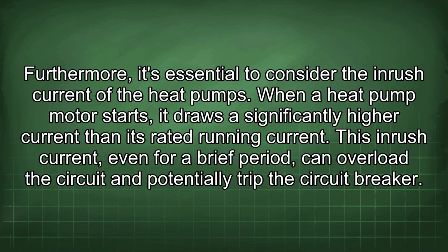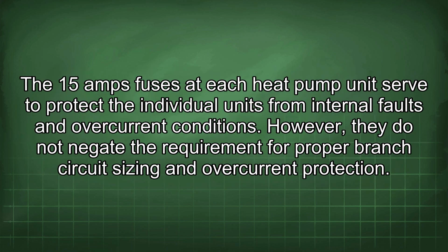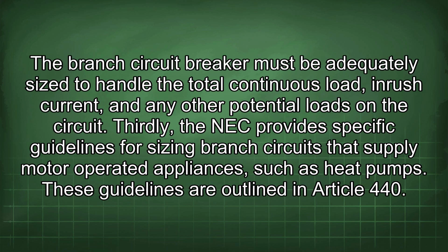Furthermore, it's essential to consider the inrush current of the heat pumps. When a heat pump motor starts, it draws a significantly higher current than its rated running current. This inrush current, even for a brief period, can overload the circuit and potentially trip the circuit breaker. The 15 amps fuses at each heat pump unit serve to protect the individual units from internal faults and overcurrent conditions. However, they do not negate the requirement for proper branch circuit sizing and overcurrent protection. The branch circuit breaker must be adequately sized to handle the total continuous load, inrush current, and any other potential loads on the circuit.